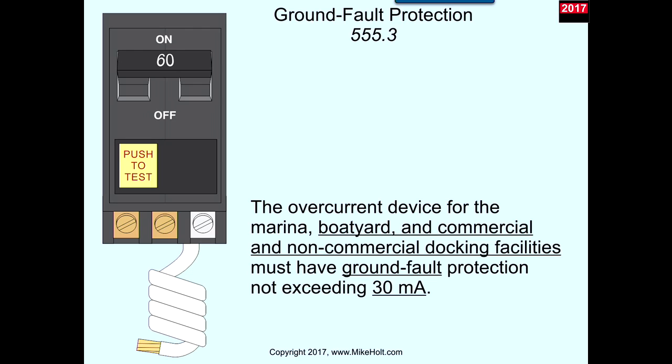The overcurrent device for marinas, boat yards, and commercial and non-commercial docking facilities must have ground fault protection not exceeding 30 milliamps.